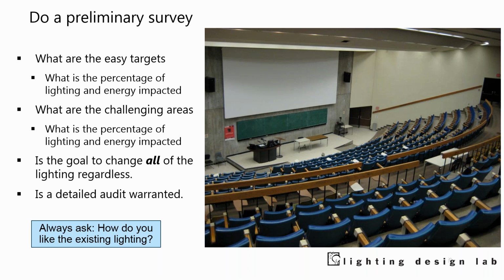In this case, they were bollards for their exterior entrance, and they really couldn't be retrofitted well. They were relatively new, and they had new modern metal halide lamps. To retrofit those would probably just mean to replace them, which would be very expensive. So we were like, you really want to do every fixture? It doesn't hurt to push on some of these a little bit.